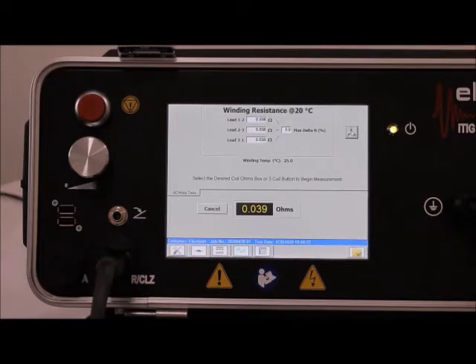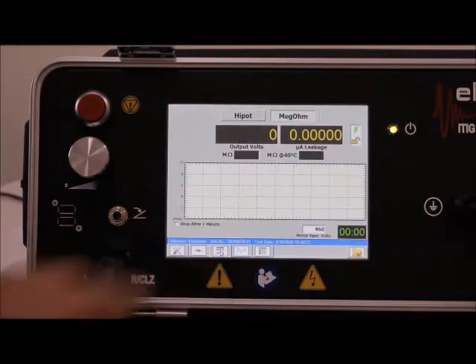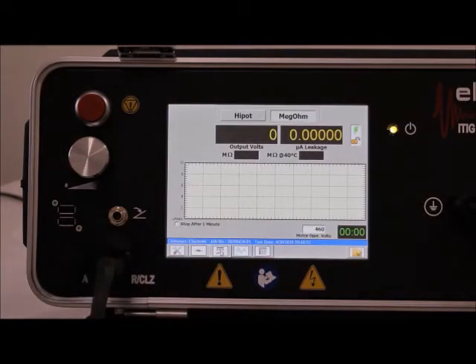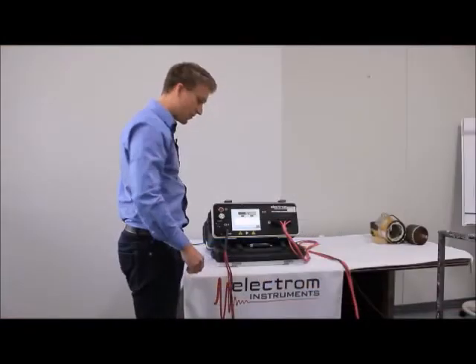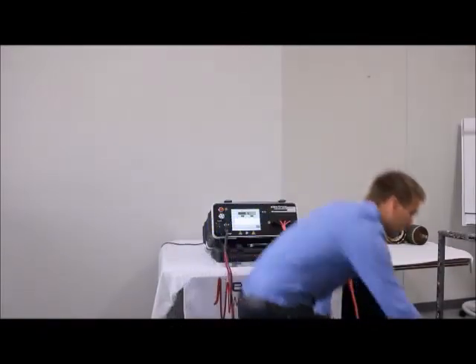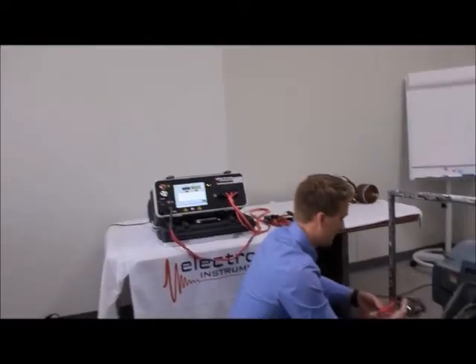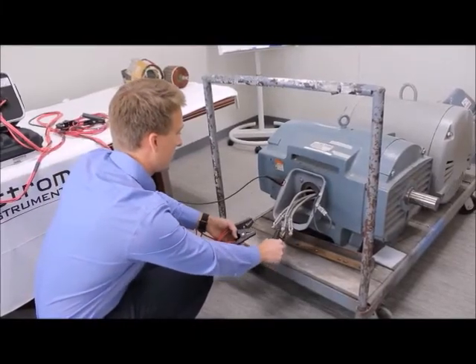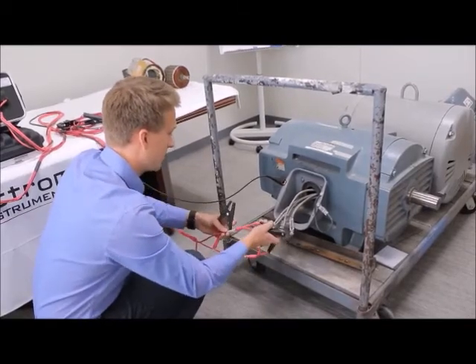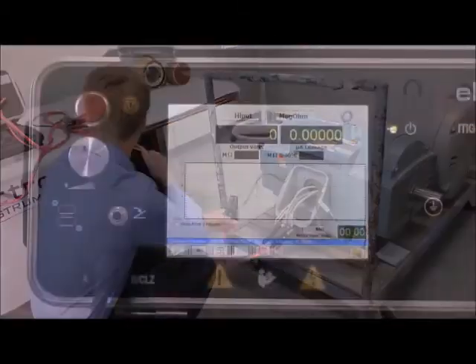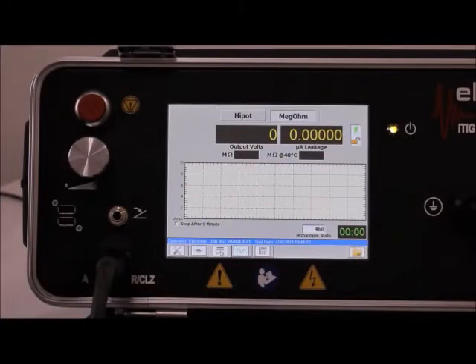Very good. We have our resistance measurements, all nice and tight. 0% max delta R. They're 0.038 ohms. That's great. Next step is our megohm measurements. Now we have to connect our high voltage lead sets. So now it's important to disconnect the low voltage lead set and reconnect our high voltage leads. So hook them onto the corresponding phases on the motor. We are good to start the megohm measurement.